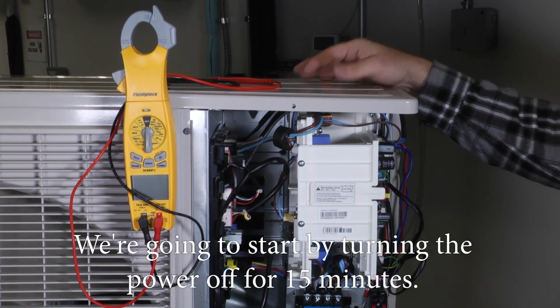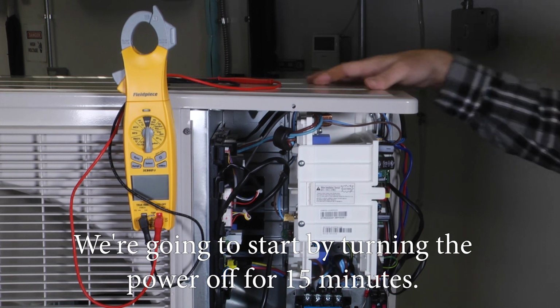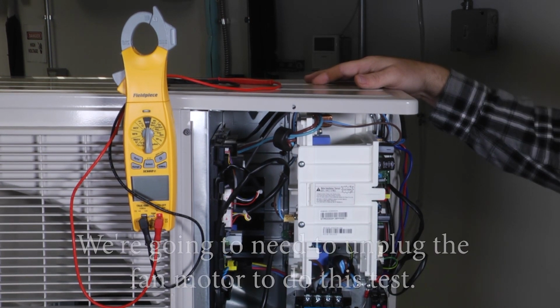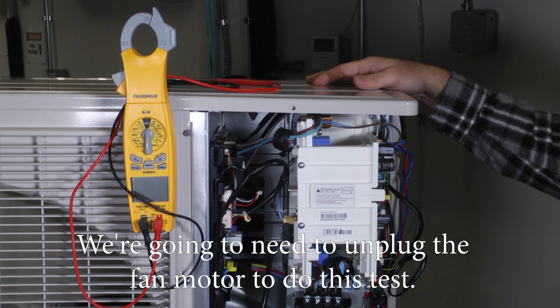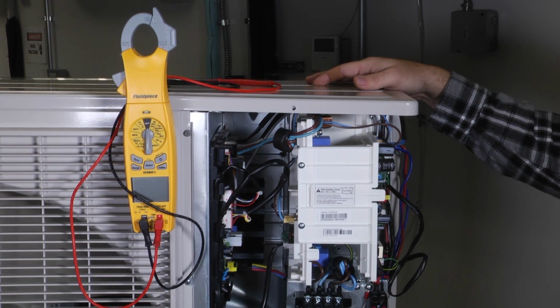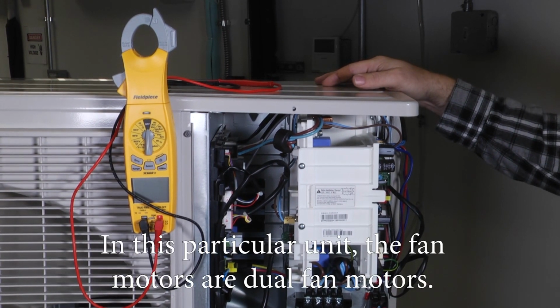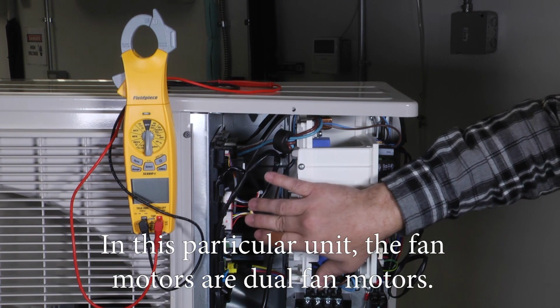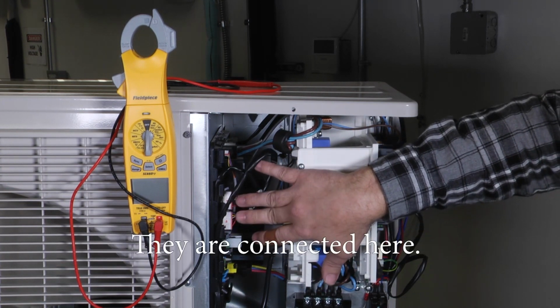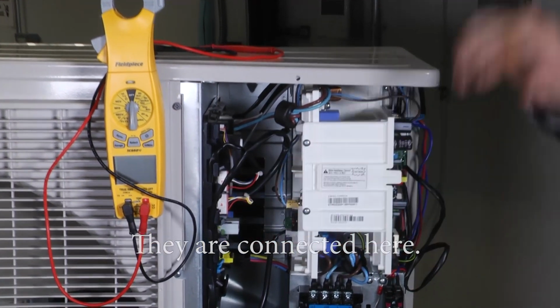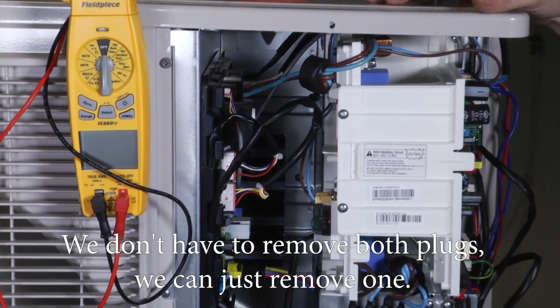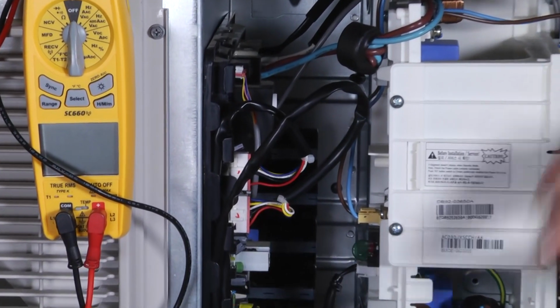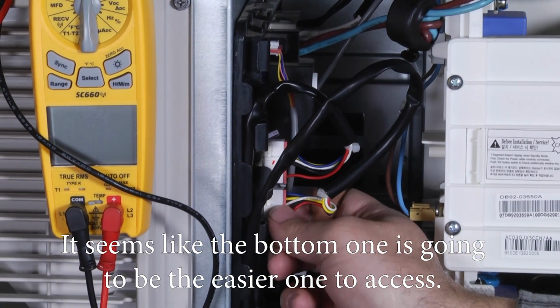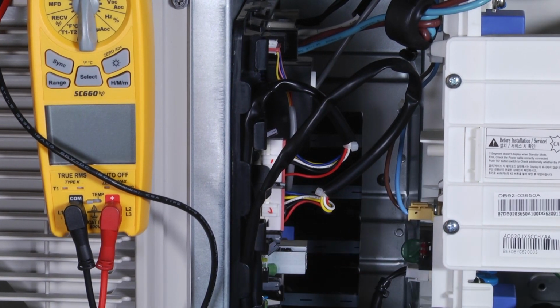But we're going to start out by turning the power off for 15 minutes. We're going to need to unplug the fan motor to do this test. In this particular unit, the fan motors are dual fan motors. They are connected here. We don't have to remove both plugs. We can just remove one, and it seems like the bottom one's going to be the easier one to access.